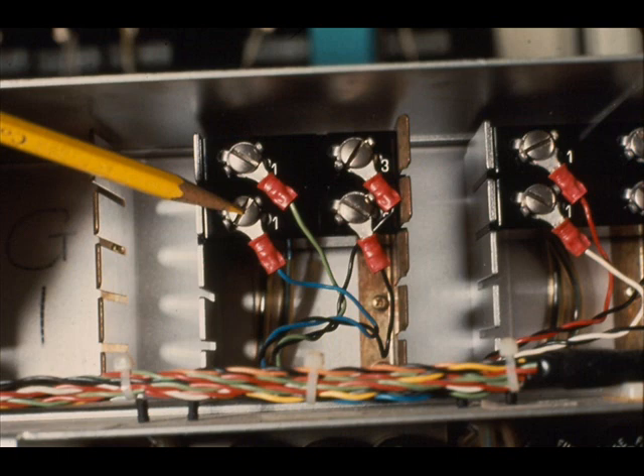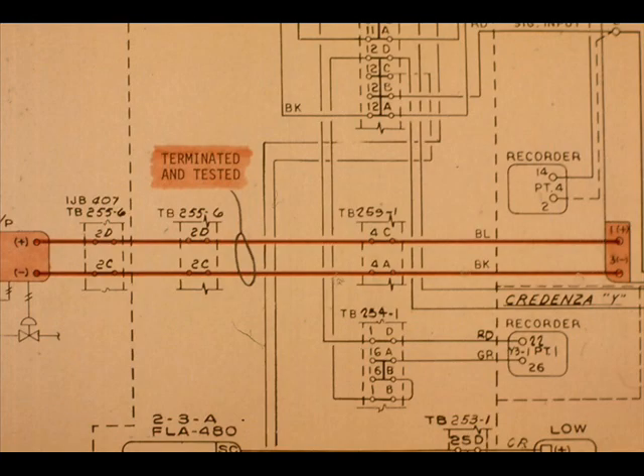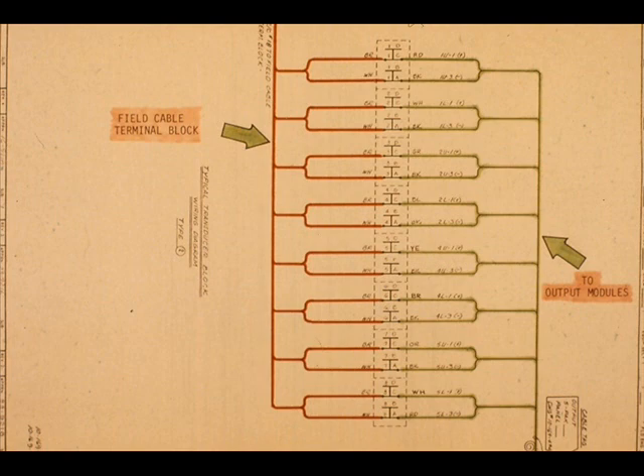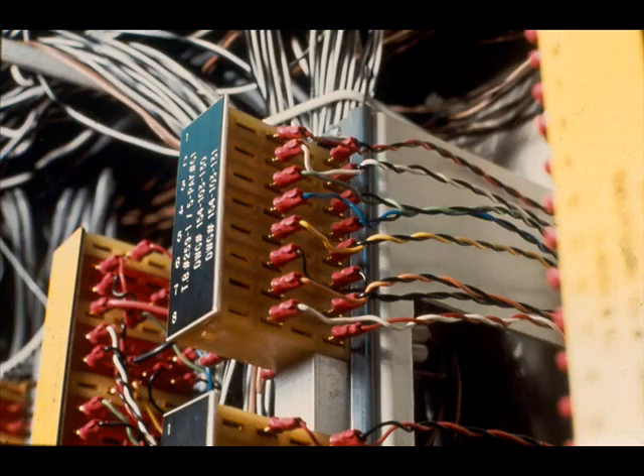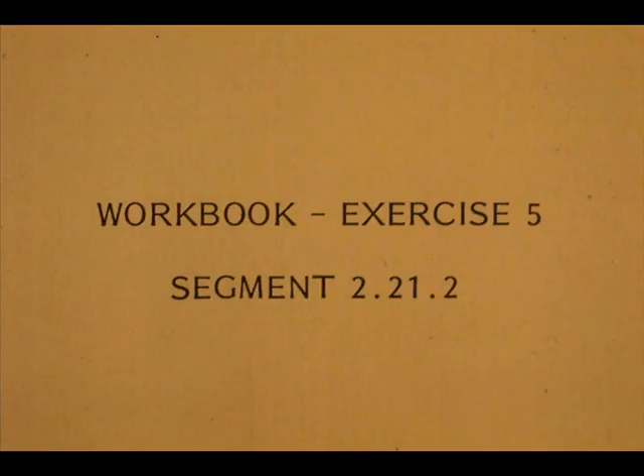Terminate the blue and black wires on the output module. Mark the loop diagram showing wires terminated and tested. Look once again at the transducer block wiring diagram. The drawing and the block wiring are identical. Now work exercise number 5 in your workbook.